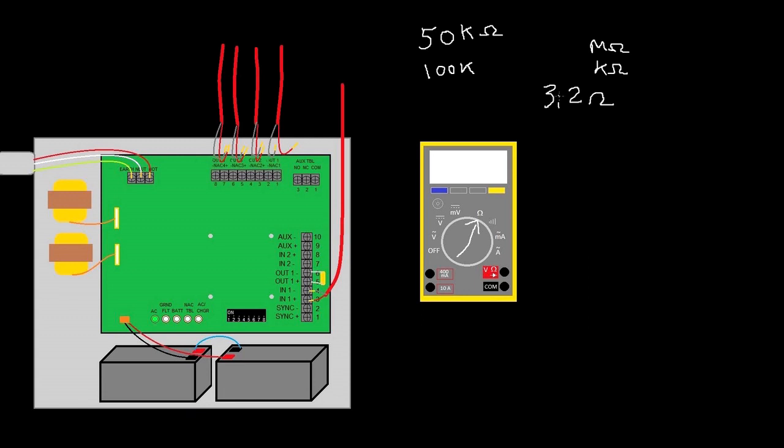If that 24 volt power somehow comes in contact with your data, that's going to cause a ground fault. But the tip is, anytime you go to meter resistance and you get a negative symbol before whatever number spits out, to me that is almost always an indication that there is either voltage present on that circuit or that there's water on that circuit.